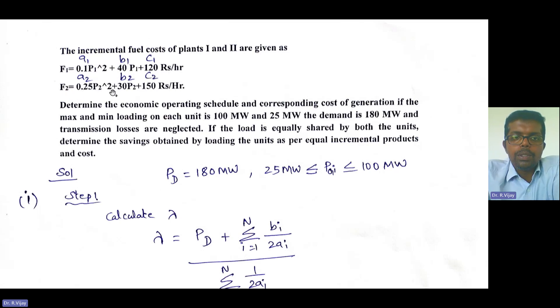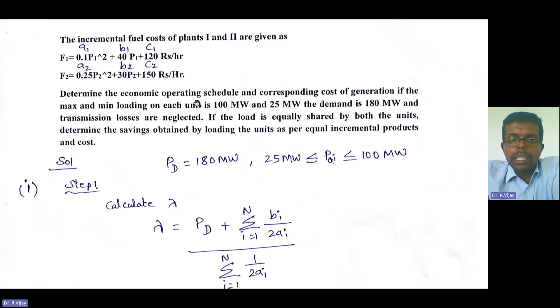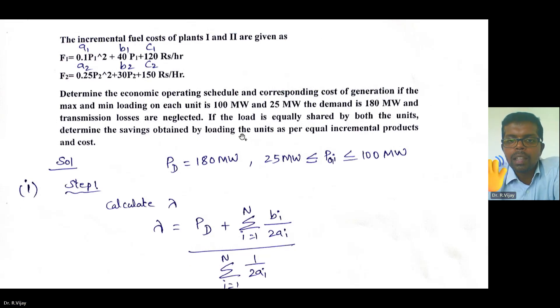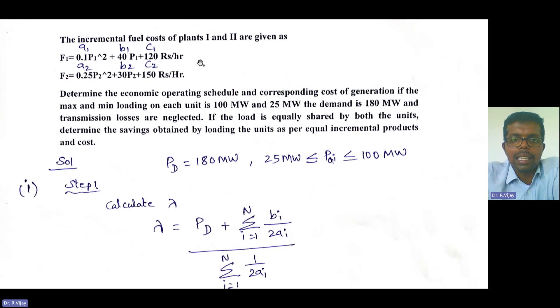F2 is equal to 0.25 P2 squared plus 30 P2 plus 150 rupees per hour. Determine the economic operating schedule and corresponding cost of generation if the maximum and minimum loading on each unit is 100 megawatt and 25 megawatt. Minimum and maximum operating limits are given as 25 megawatt to 100 megawatt. Demand is given as 180 megawatt and transmission losses are neglected.